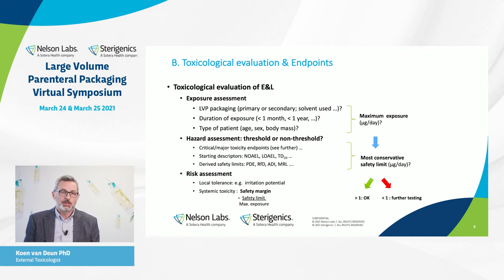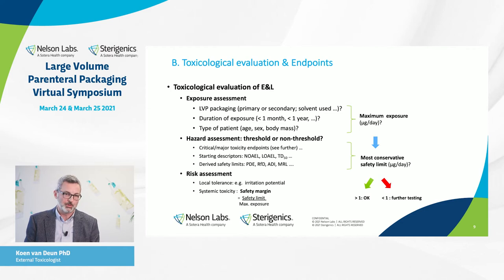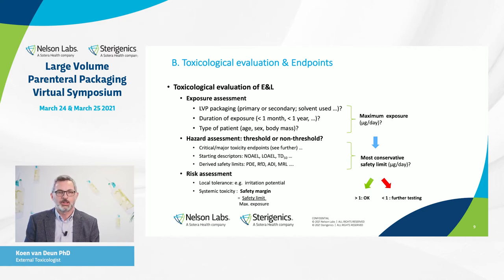Another important factor in the exposure evaluation is the duration of exposure. If it's less than one month, this can be taken into account in the calculations for a permissible daily exposure value. Whereas when it's lifetime exposure, we have to apply much larger safety factors than for one month. Finally, the type of patient is important: if it's for adults, which is the typical situation, this is taken into account. But if it's for children or neonates, we have additional adaptations in the body weights.